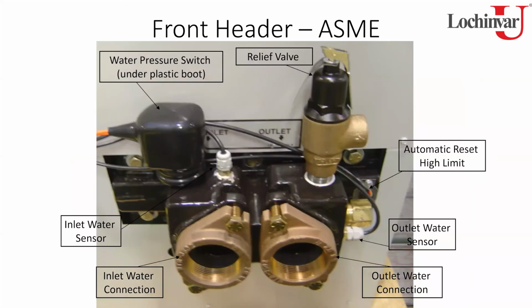And if we look at the ASME, very similar, again, just a different design on the head. Still got the same inlet and outlet connections, still the same sensors, just different locations, with that outlet sensor kind of stuck in the side there. Same thing for that automatic reset high limit. Come back here on the back a little bit. So a little bit different there. And then you also see a relief valve here. So that's something you typically don't see on the non-ASME.